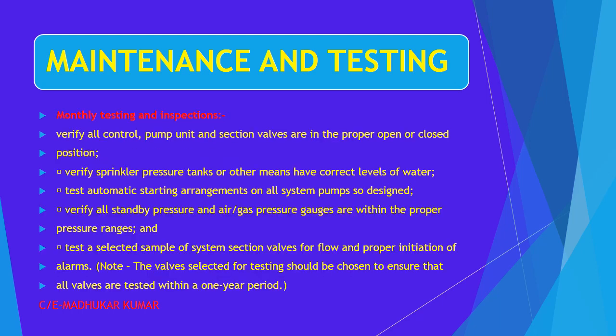In continuation, now monthly testing. Verify that all control pump unit and section valves are in the proper open or closed position. In continuation with that, monthly we also have to continue with this practice. Verify that sprinkler pressure tanks or other tanks have the correct level of water or correct pressure. Test the automatic starting arrangement on all system pumps so designed. When we have an automatic system, the automatic operation must be tested on a monthly basis. Verify that all standby pressure and air gas pressure gauges are within the proper pressure range. Sometimes these malfunction, so if required change them, otherwise check that they are working properly. Test a selected sample of system section valves for flow and proper initiation of the alarms.